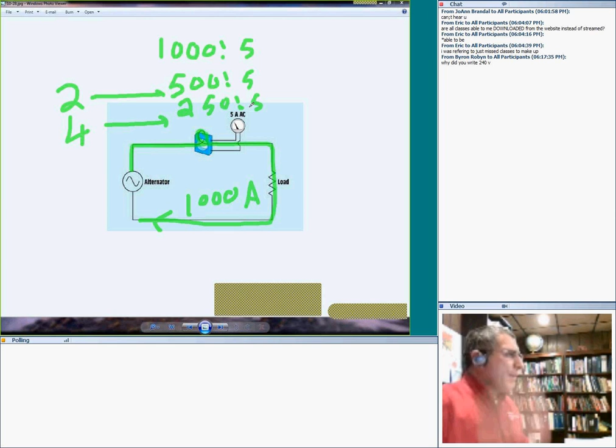Now you might ask, why would I do something like this? It's for more sensitive equipment. A 1000 to 5 CT is not good sensitivity - if my full load amp is 50 amps, it's not sensitive enough. So to change the sensitivity of the CTs, what you do, which is not practical, is loop them. We never actually do that.